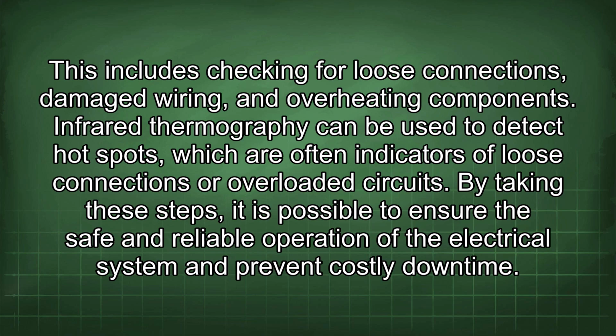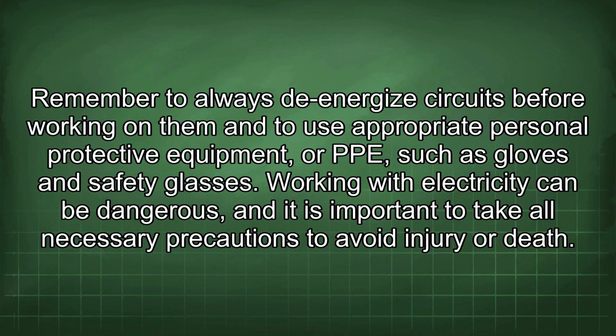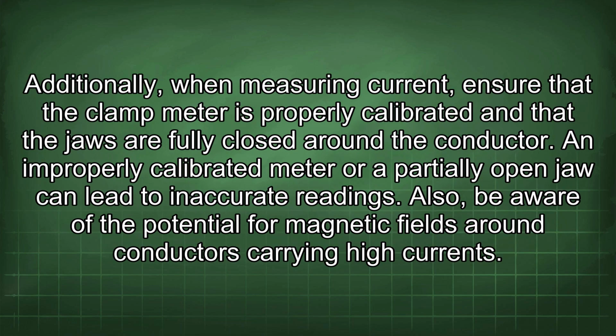costly downtime. Remember to always de-energize circuits before working on them and to use appropriate personal protective equipment, or PPE, such as gloves and safety glasses. Working with electricity can be dangerous, and it is important to take all necessary precautions to avoid injury or death. Additionally, when measuring current, ensure that the clamp meter is properly calibrated and that the jaws are fully closed around the conductor. An improperly calibrated meter or a partially open jaw can lead to inaccurate readings.